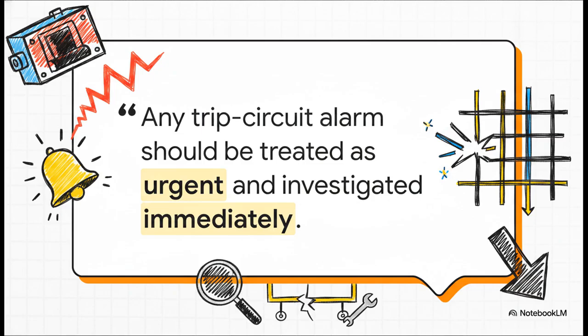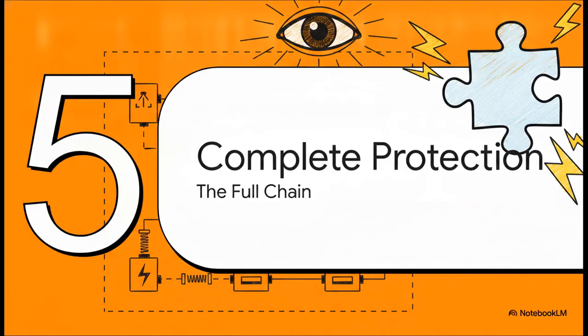Rule of thumb. Any trip circuit supervision alarm must be treated as an urgent, immediate threat. It does not mean something might break soon. It means the breaker is effectively crippled right now. If a genuine trip command comes in while that alarm is active, the breaker will not operate. The grid is essentially unprotected in that zone. You investigate it immediately. Section 5.